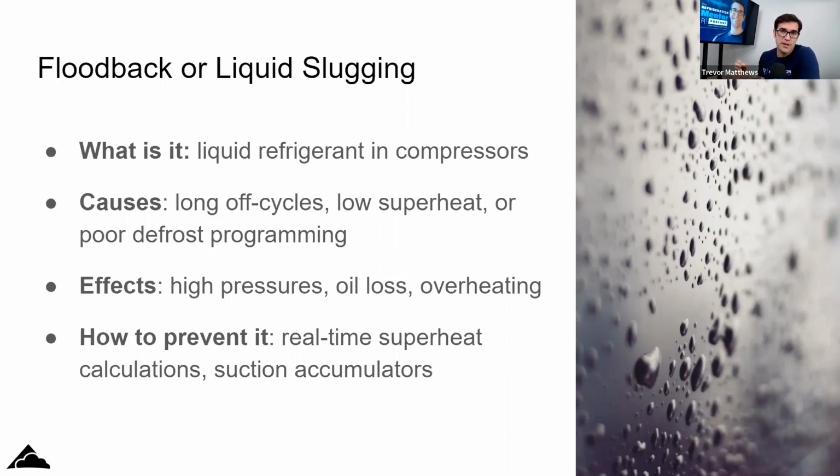So checking your, like Joe was saying, your system superheat. You can call it compressor superheat as well, knowing exactly what's happening to that compressor. You get discharge superheat as well to tell if liquid is condensing inside the compressor. So there's so many different analytics you can do. It's happening now, especially on the newer systems, like I said, in CO2 refrigeration.